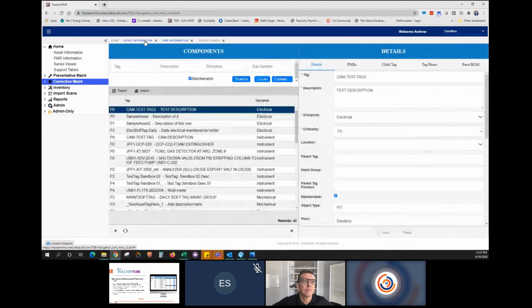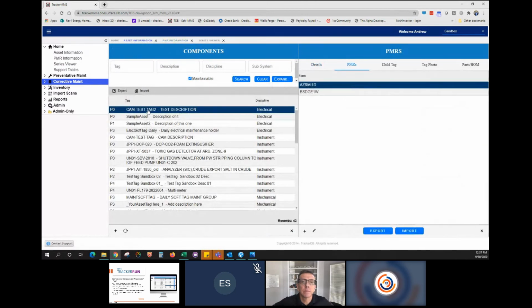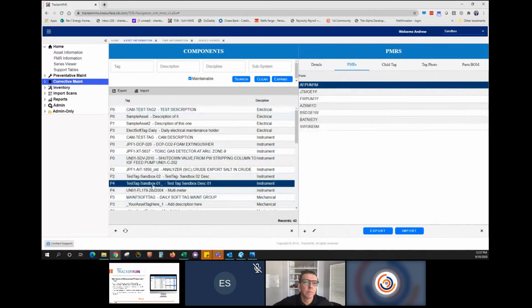When you go into the tag section, there are multiple ways to do this, but I'll go over to the PMRs for this particular tag, and we'll pick test tag 01 down here. I can already see the switchgear electrical 6-month here. I can go add a new PMR, pick from the list of PMRs, and add it. During that process you can pick the start date for the maintenance and the frequency, whether you want to generate it every day, every 30 days, every 180 days - totally up to you.